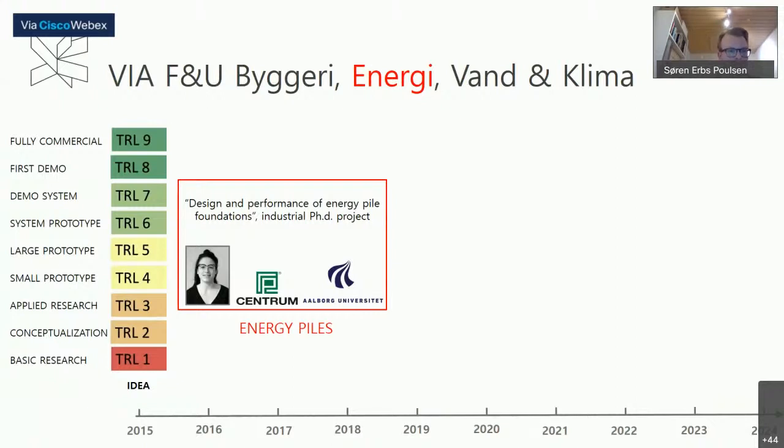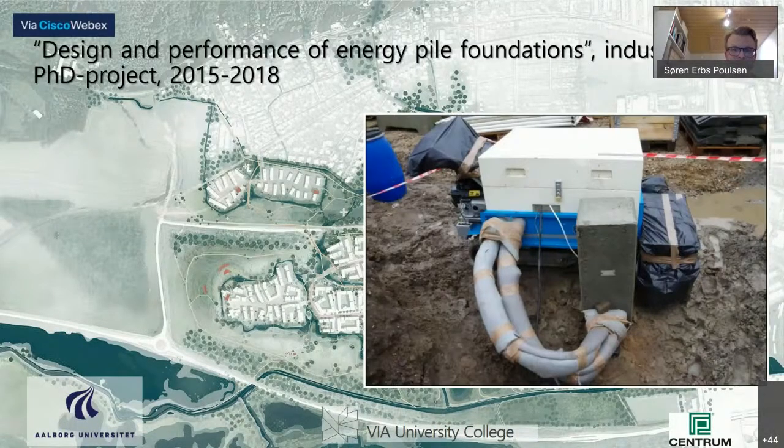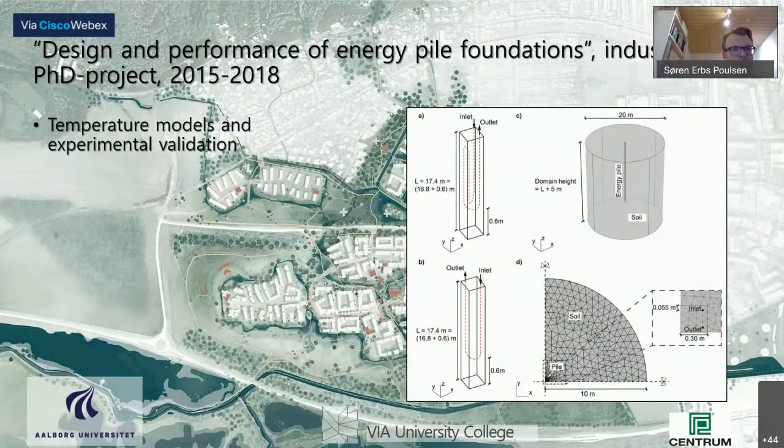Maria started out at quite a low TRL level. The energy piles produced in Denmark by this company, Centrum Pæle, they didn't know anything about the thermal performance of the pile. So we started out at around TRL 3. Maria did a lot of fieldwork testing energy piles with our thermal response test equipment at VIA. Then she tried to model that thermal behavior that she was measuring in the real world with finite element modeling. She was able to develop these G-functions for energy piles, which are dimensionless temperature functions that we use to describe the thermal behavior of the pile.